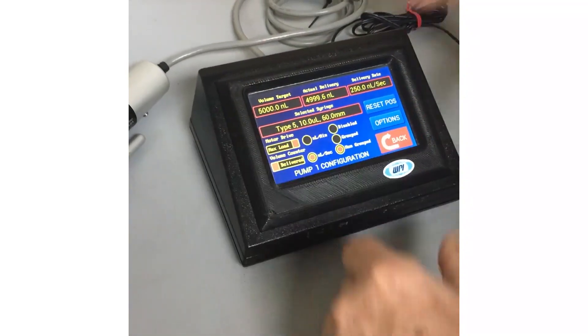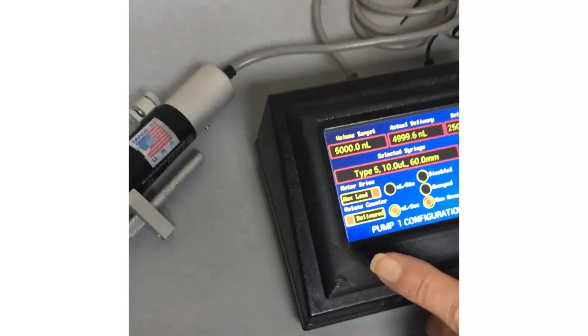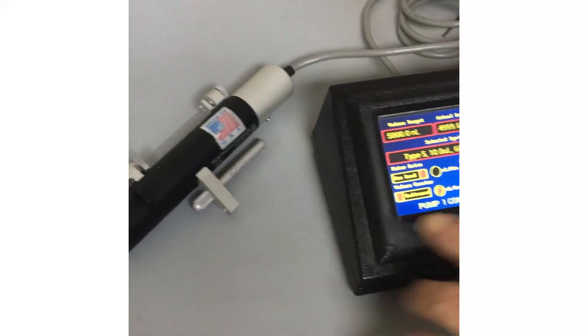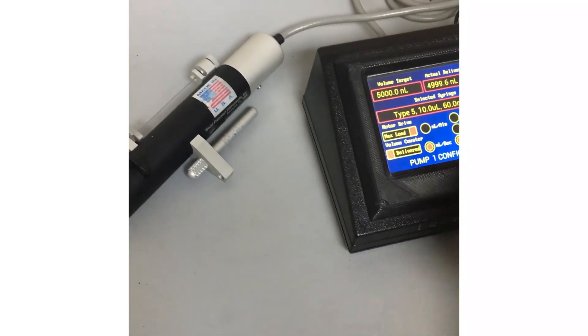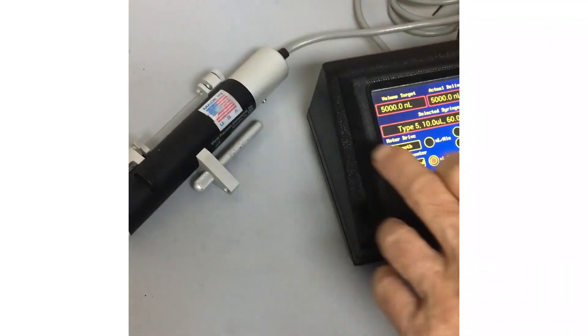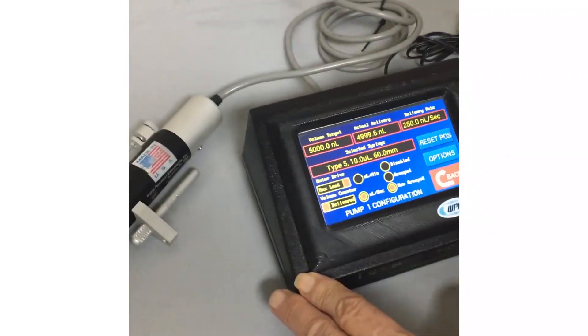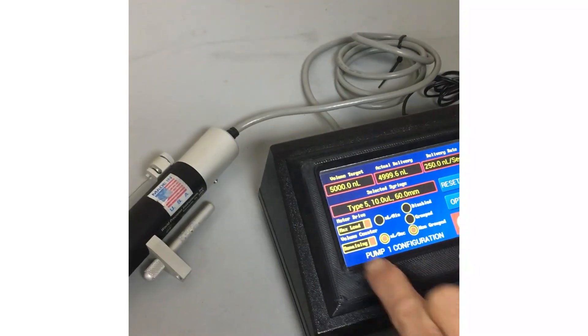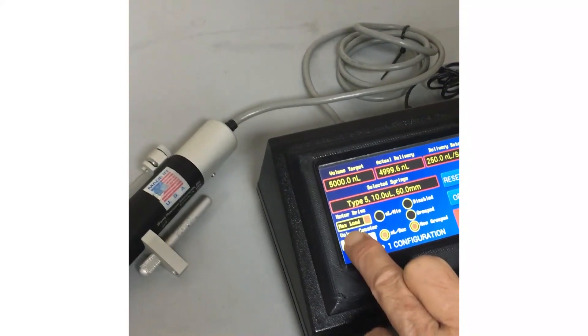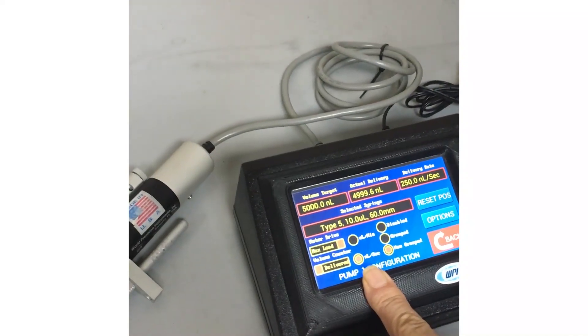Let's just leave the delivery rate and volume alone. I'm going to leave this on max load for the time being because there's a bug in the software — when you go to nanoliters per minute in the smooth mode, it loses track. So let's leave it in max load. We've got to get a new firmware update. For actual delivery or remaining, we usually just leave this in actual delivery in nanoliters per second.